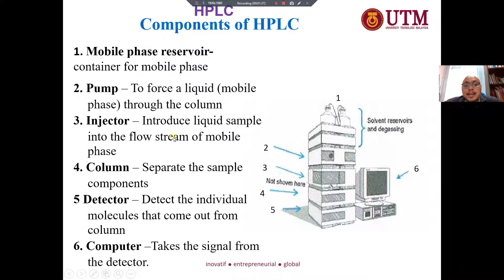The mobile phase reservoir is the container for the mobile phase, located higher than the pump. The container must be located higher than the pump to aid the flow. The tubing that delivers the mobile phase has a frit at the end to filter any undissolved solids or particulates. So in the bottle, we have the frit over here. This small one we call the frit. The function of the frit is to filter any undissolved solids or particulates before they enter the system.